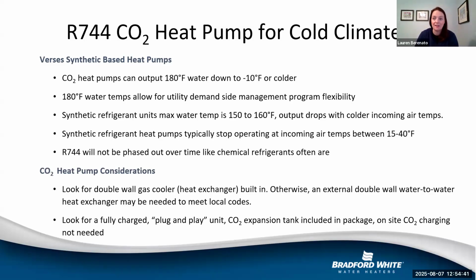So you likely will have it tempering down, but your synthetic refrigerants operate at a maximum water temperature of 150 to 160, and then it will also drop down again at 15 to 40 degrees when your incoming air temperature is in that range. The R744 will not be phased out over a timeline like chemical refrigerants often are. For CO2 heat pump considerations, you are going to look for double wall gas coolers with a heat exchanger built in, otherwise an external double wall for the water, and look for a fully charged plug and play.